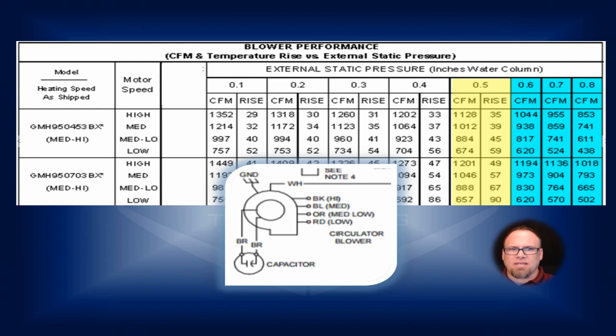And then lastly, make sure that everything is set up properly. Do we have a blower? Is our blower set up the way that it should be? Do we have the right dip switches selected on a variable speed or ECM blower? And then in addition to that, do we have the right CFMs on a multi-speed blower for the amount of tonnage that we have on this equipment?